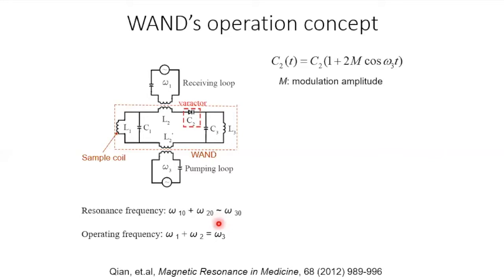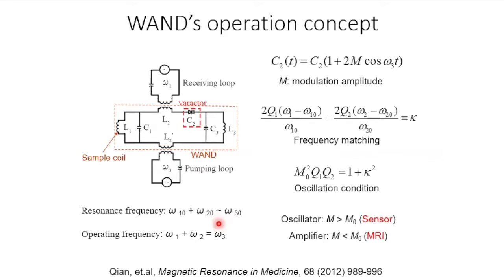This is because when we make the sensor and embed it into the body cavities, we can no longer retune it. But this is not a problem because as long as we can satisfy a certain relation to make the off-resonant effect at one resonance frequency equal to the off-resonant effect at the second resonance frequency, then we can effectively make the sensor perform efficiently at the particular operating frequency. This is what we call the frequency matching condition. And by fine-tuning the pumping signal to make the square of the modulation amplitude multiplied by the quality factors equal to 1 plus kappa squared, efficient oscillation can occur.